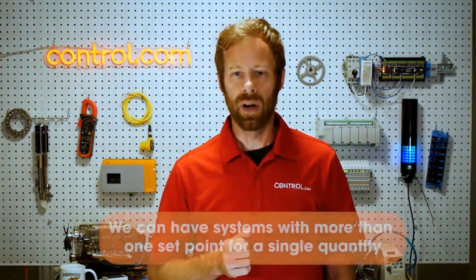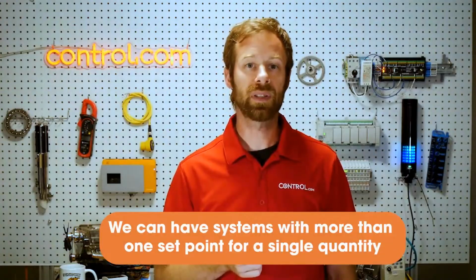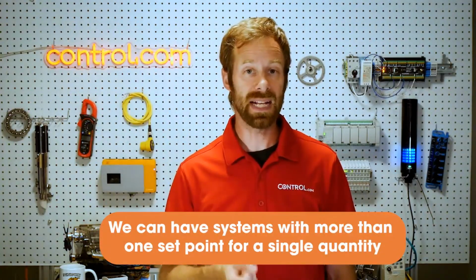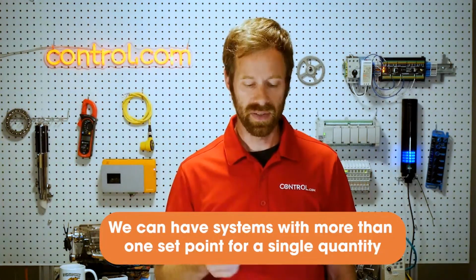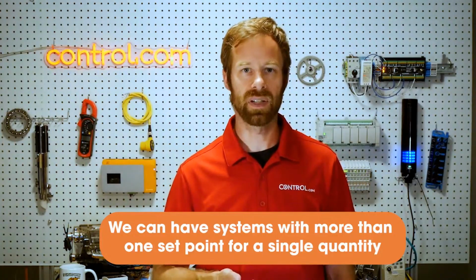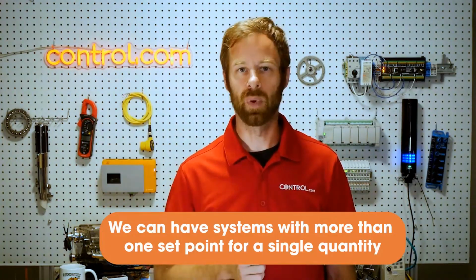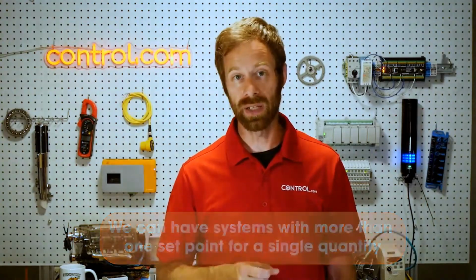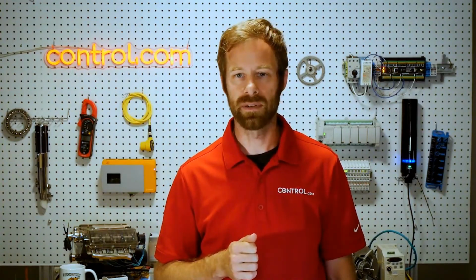I mean, if they were completely better than digital in all aspects, then we wouldn't have digital sensors, we would only have analog, but that's not the case. We only design for the system as we need it. We can also have systems with more than one set point for a single quantity, and that's really important, something that the discrete sensors cannot give us: more than one set point per sensor. Analog can do that, and a couple of others that we're going to talk about here in a little bit. They can provide us more information.